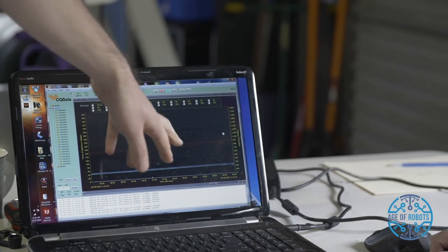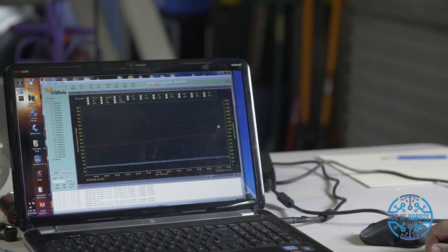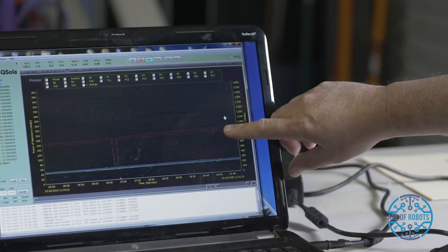And because we can see that, you can also see which panels are damaged and actually disable a single panel. If you need to, you can take that out of circuit and have the rest of them work as normal. There's a lot of remote working that you can do with this. From the remote side of things, we can turn off the system, and we can do testing to see whether or not we're at the maximum power point. We can actually see whether or not we're collecting the most amount of power out of the solar farm. We're the first people that can actually do that test. That'll give you this W curve in the line, so we call it the W test.